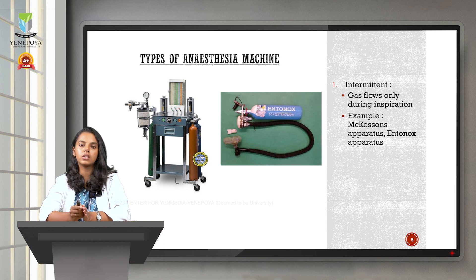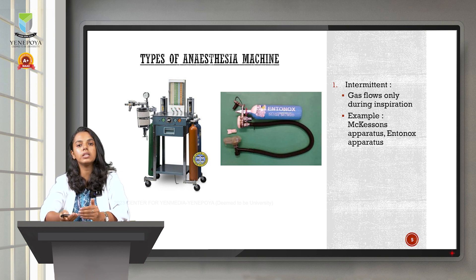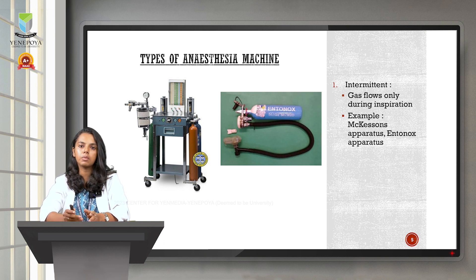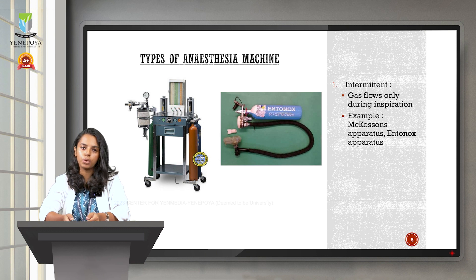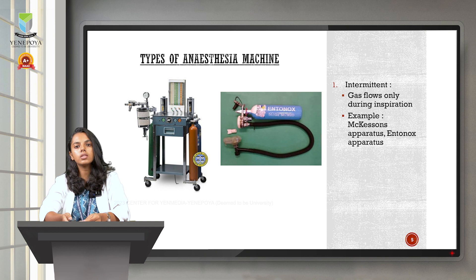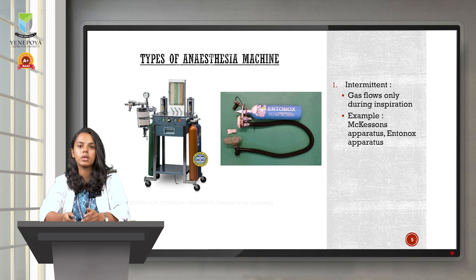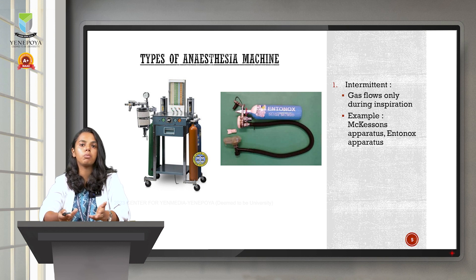There are two types of anesthesia machine. The first type is the intermittent anesthesia machine, in which the gas flow occurs only during inspiration. Common examples are McKesson's apparatus and Entonox apparatus. McKesson's apparatus is no longer used — it was used in ancient times — whereas Entonox apparatus can still be seen in hospitals today. Entonox is a mixture of oxygen and nitrous oxide in equal proportions, which acts as an analgesic and is used during labor pain in pregnant women.